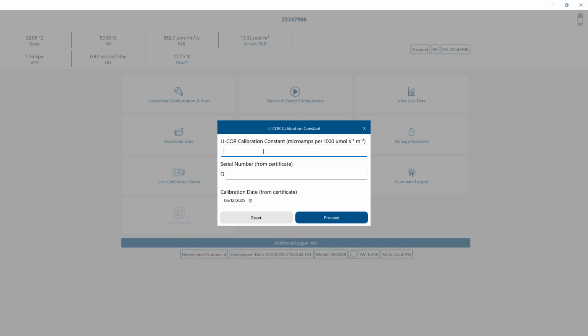That constant will be somewhere between 5 and 10 microamps per 1000 micromoles per second per meter square. So you will enter that value, let's call it 5.5. You enter that serial number so you can have it for reference, because that information will be logged, and you can select the date. This is a nice way to have reference, so that a couple years down the line, you know exactly when this calibration date started. It's always going to be part of your exported data. It's a great way of entering that information without having to send the device back or use any third-party software.